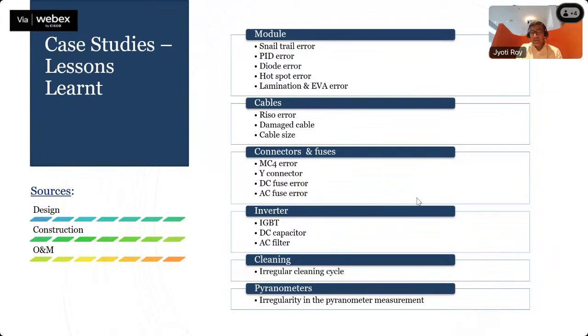We observed that in most Indian projects there are always a few spare terminals available at the combiner box or inverter level. So we suggested running a parallel cable system, terminating both ends at the combiner box and the inverter—safety being the prime factor in any site intervention—connecting both ends during low irradiance hours, like the afternoon. This not only uplifted performance but maintained sustainability against that design error for the life of the project.